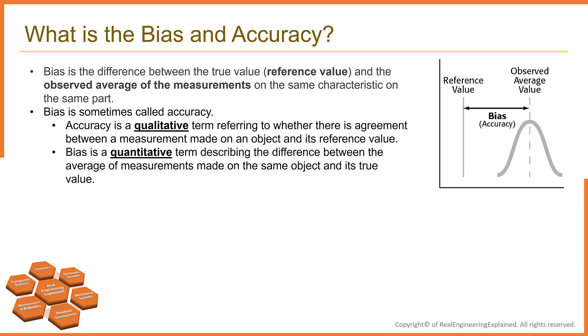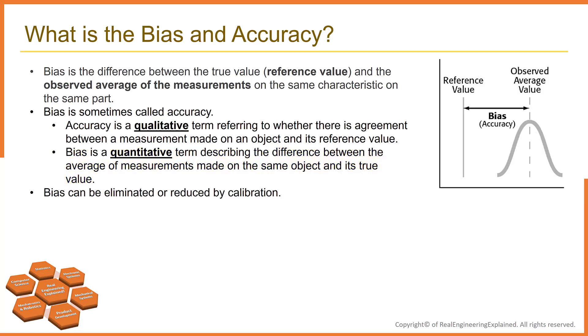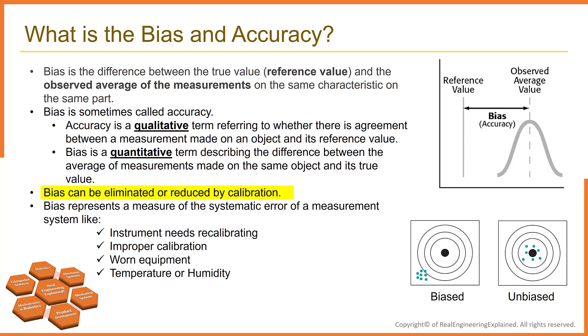Bias is a quantitative term describing the difference between the average of measurements made on the same object and its true value. Bias can be eliminated or reduced by calibration. However, errors that contribute to bias can be present even where all equipment is properly calibrated and under control. Temperature probably has the most potential for introducing this type of bias — for example, a constant heat source will introduce serious errors in dimensional measurement of metal objects.